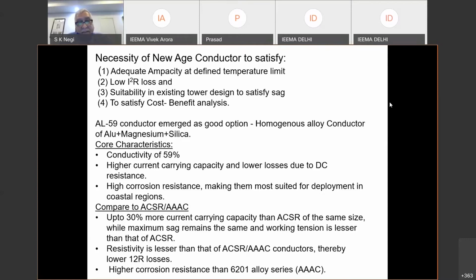Then higher current carrying capacity and lower losses due to DC resistance. AL59 has high corrosion resistance, making it most suited for deployment in coastal areas. That was a very important factor for us because in the coastal areas, there is corrosion of the conductor, both steel and even aluminum also. There is a white rust on that. So this came in handy, the AL59 conductor, which has a high corrosion resistance.